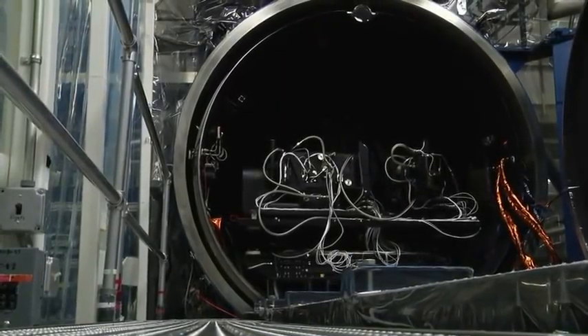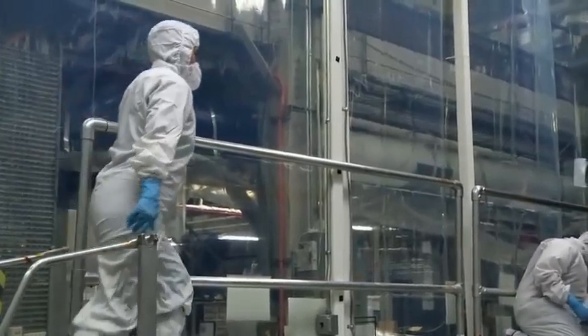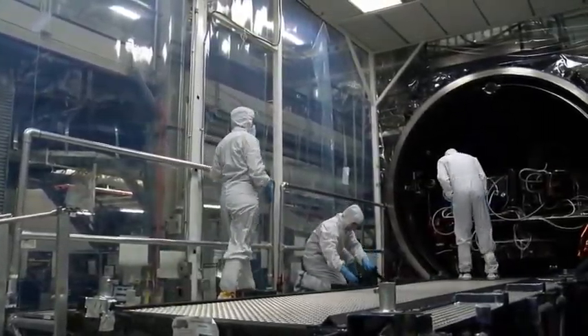Because TIRS is a thermal instrument that measures temperature from space, we do our testing in a thermal vacuum chamber where we can control the temperature and pressure.